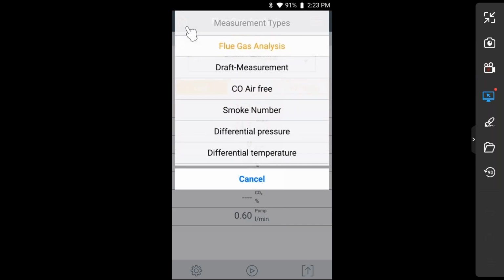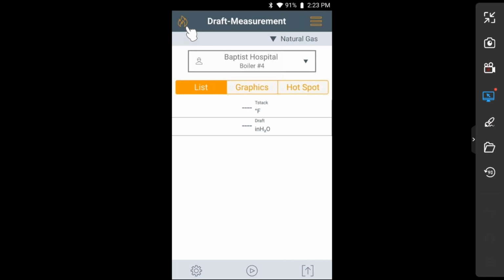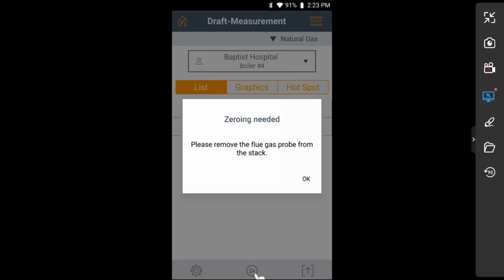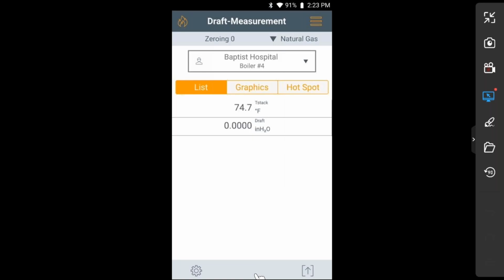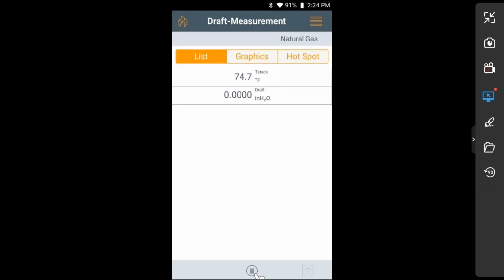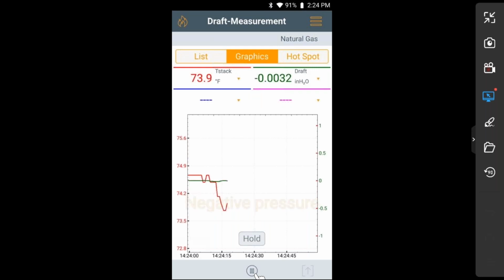The 3 measurements you're going to be doing a lot are certainly the flue gas and the draft measurement. If I hit the draft measurement right now, I'm going to do a draft test, and I'm going to hit this button on the bottom here, which is going to turn that on, and it's going to tell me to take the probe out of the stack and press OK, because I'm zeroing the pressure sensor to the atmospheric pressure. You can see right now it's 0, 0, 0. So I can move this probe back and forth, and I'm creating some pressure. Now I can also look at this in graphic form as well. You can see how that measurement's jumping up and down as I move the probe. I can hold the display, and when I hold the display, I can print this information or store the readings.